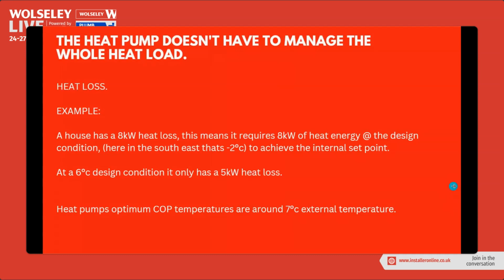As you raise up the country, the design temperature increases. So at -2, I need 8 kilowatts of thermal energy to get my room to 21 degrees. However, it's not -2 for that long. I know it's really cold at the moment, probably not doing me any favours at the minute, but it's not actually -2 for that long. Maybe 2 weeks of the heating season, it's actually -2.